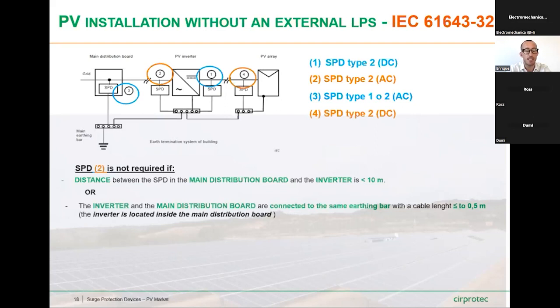Then there is an additional SPD required in the location 4, close to the PV array, that should be a DC SPD type 2, and this one will not be required if the distance between the inverter and the PV array is below 10 meters.